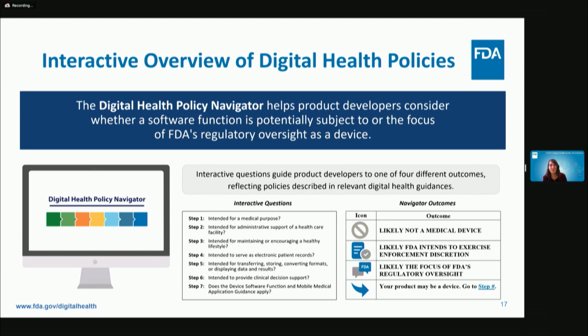And this is a public facing tool to help in determining whether a product's software functions are potentially the focus of the FDA's oversight. So it includes seven steps, each with a set of yes or no questions intended to guide you through relevant device regulatory considerations. So these steps lead to 4 different outcomes, which reflect the policies described in the guidances. And they include likely not a medical device. So this means a software function likely does not require FDA clearance before going to market. Likely FDA intends to exercise enforcement discretion. In this case, review the guidances, make sure the software function falls within the policy. If it does, you likely can market the product without engaging the FDA, or likely the focus of FDA's regulatory oversight. In this case, the software function is likely a device and the focus of FDA's oversight, which may involve a pre-market submission prior to marketing your product.